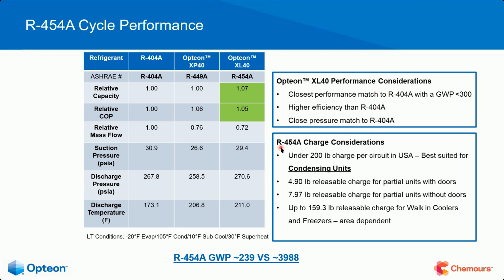Now, for 454A charge considerations, under 200-pound charge per circuit in the USA, best suited for condensing units. Now, when you use these in condensing units, you're going to have, and I'll get into this later, what releasable charge means. You're only going to be allowed a 4.90 pound releasable charge for partial units with doors, and I would even throw drawers in there. So doors and drawers. Systems condensing units without doors and drawers, open cases, releasable charge will be 7.97 for obvious reasons. If you can't trap the gas, they're going to allow you a little more releasable charge. And again, I'll explain releasable charge here in a little bit.